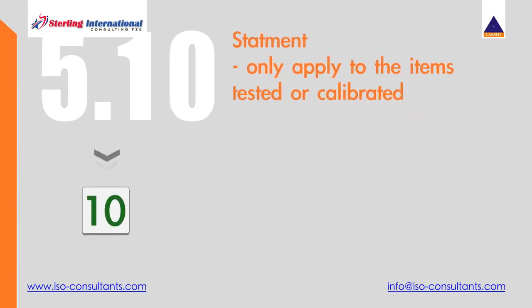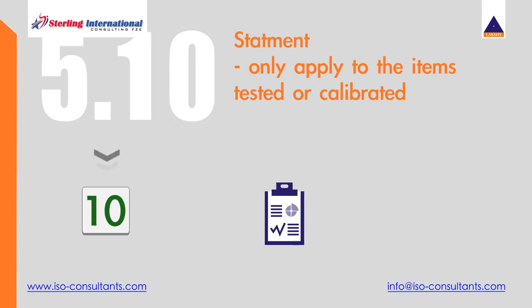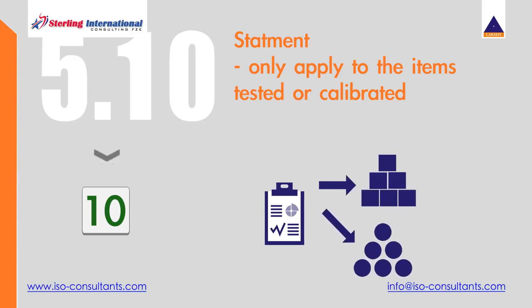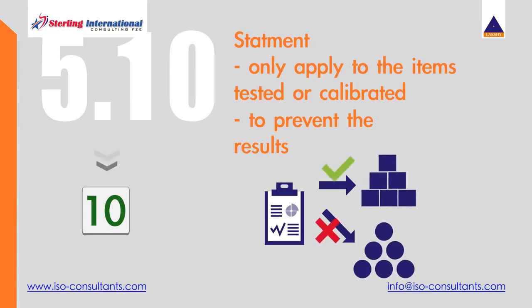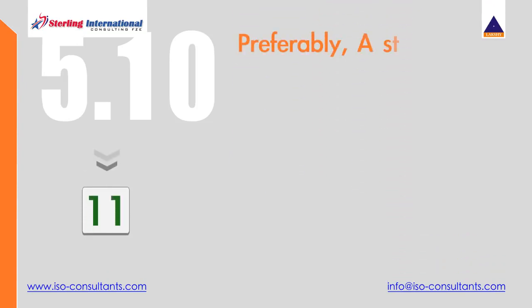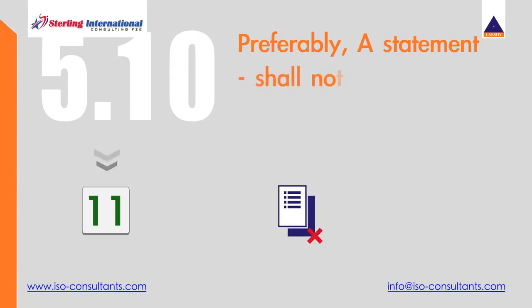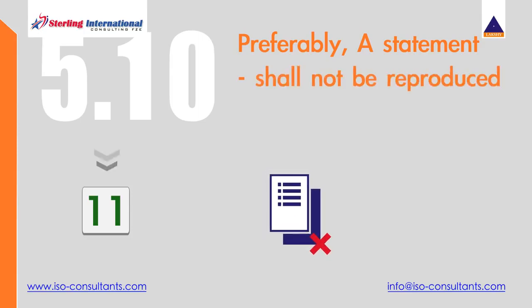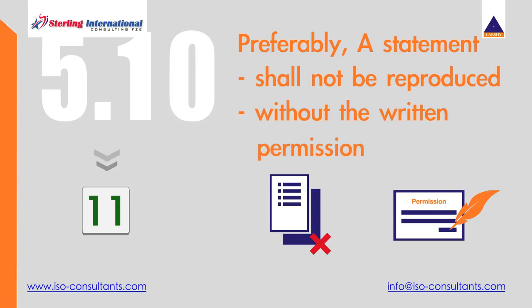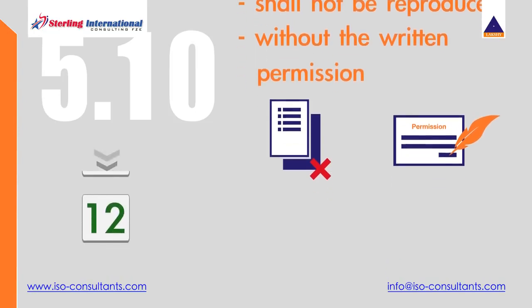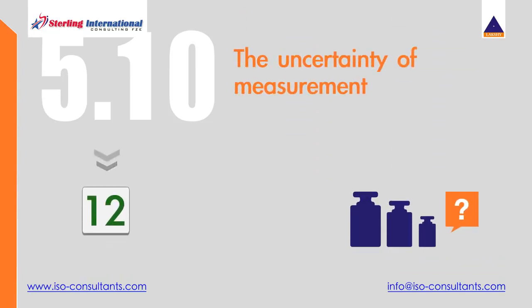Where relevant, a statement that the results only apply to the items tested or calibrated. This is generally required in the case of product testing to prevent the results being applied inappropriately in support of general product or batch certification. 11. Preferably, a statement that the report shall not be reproduced except in full without the written permission of the laboratory. 12. The uncertainty of measurement.